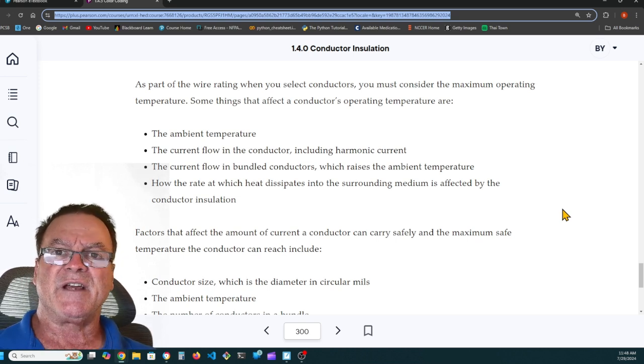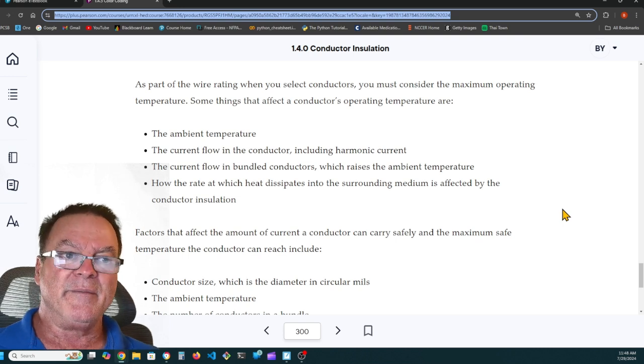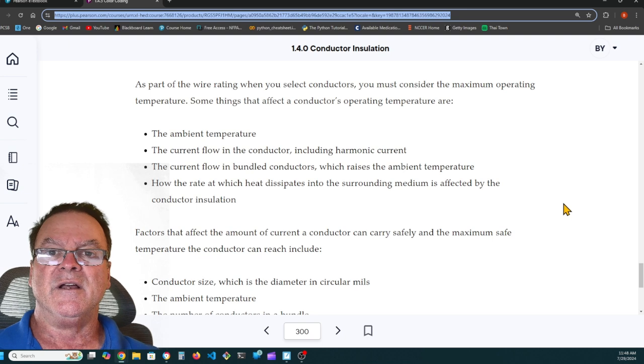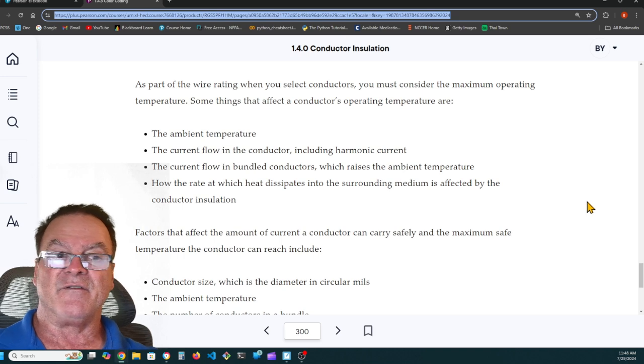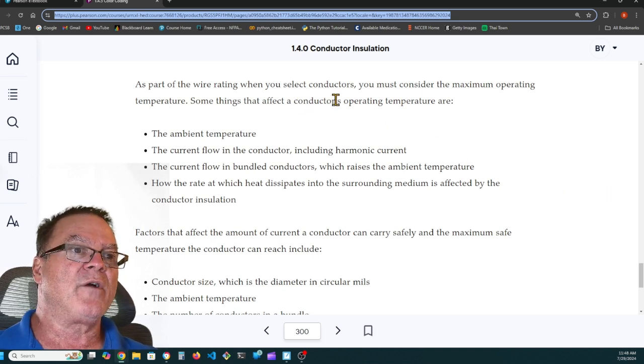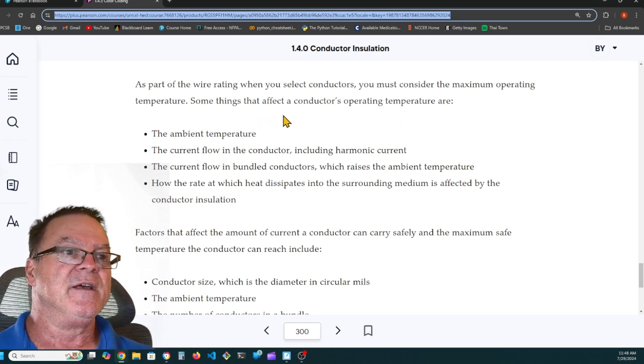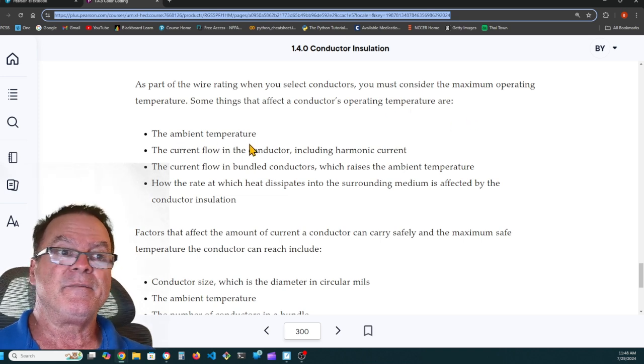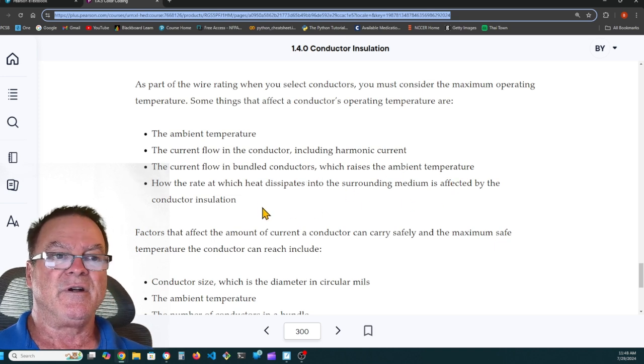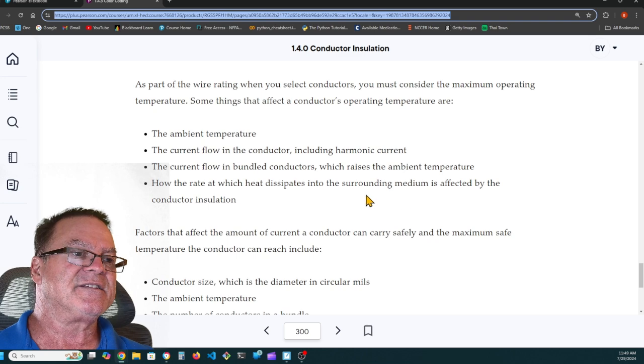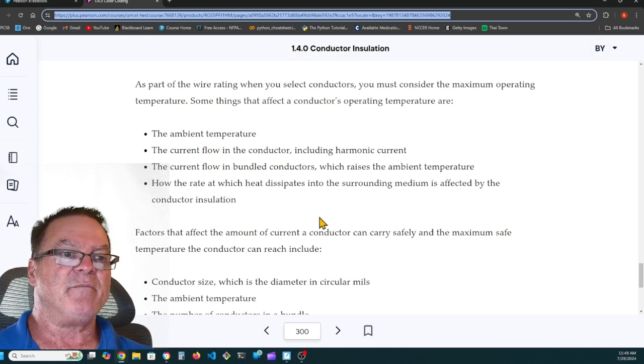So we want to make sure that we protect the insulation of the wire by limiting the amount of current flow through the wire to keep the temperature below the rating of the insulation of the wire. As part of the wire rating, when you select a conductor, you must consider the maximum operating temperature. Some things that affect a conductor's operating temperature are the ambient temperature, that's the air around us, the current flow in the conductor, including harmonic currents, the current flow in bundled conductors, which raises the ambient temperature, and the rate at which heat dissipates into the surrounding medium, which is affected by the conductor insulation.